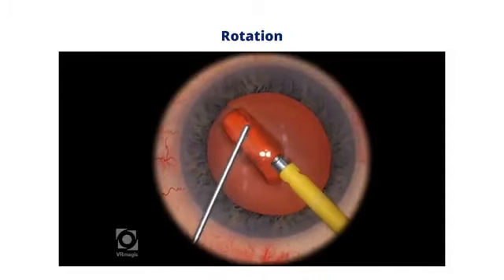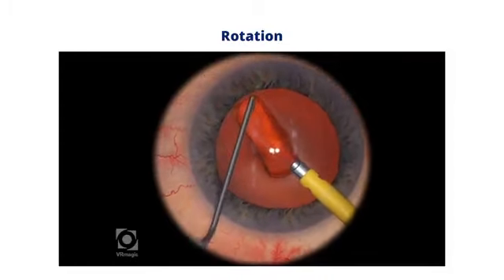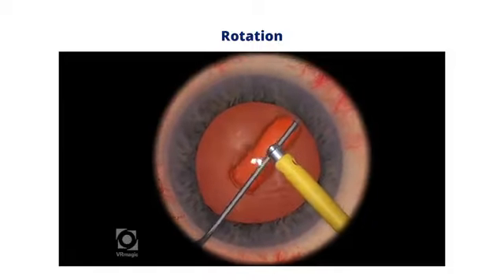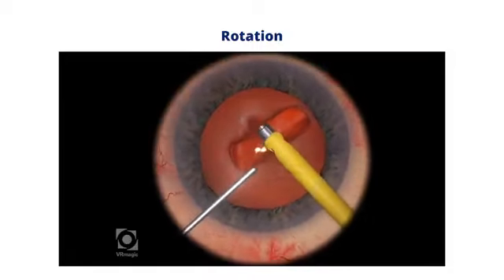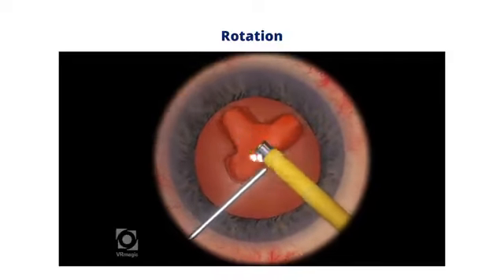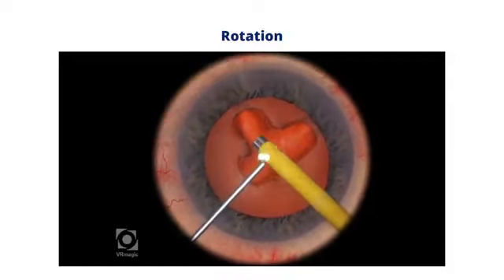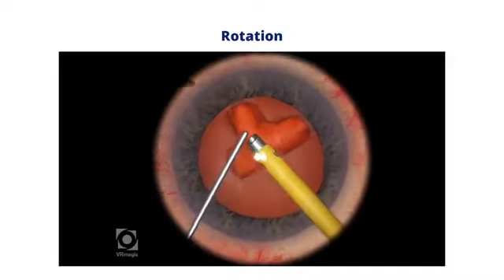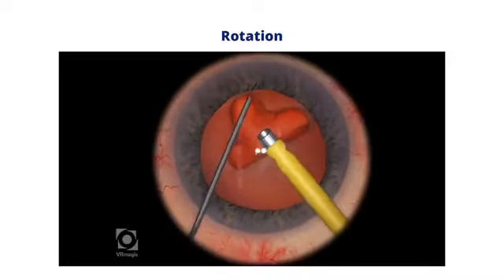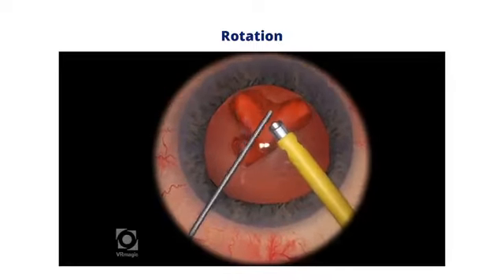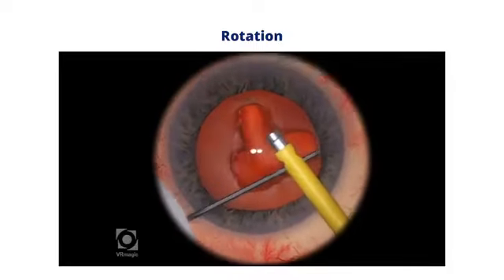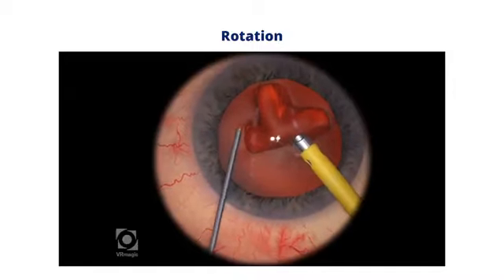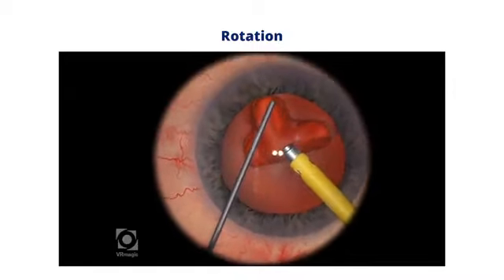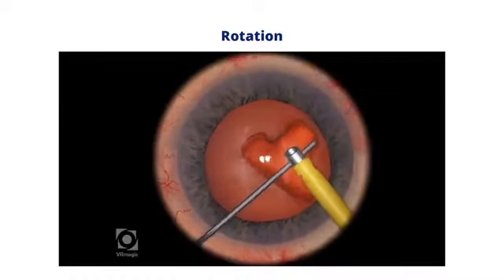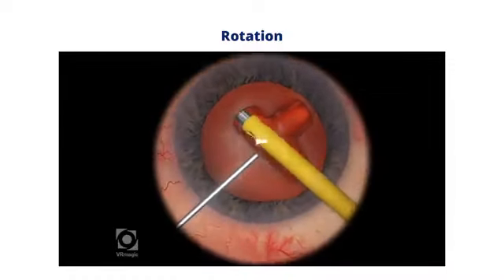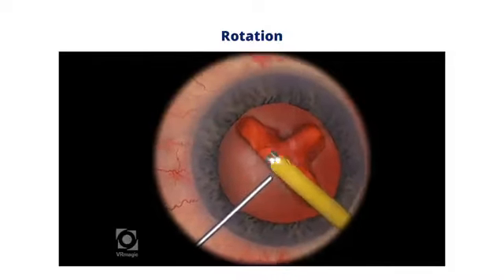When the first trench has been completed, the nucleus is rotated 90 degrees to make the second groove. The nucleus is rotated by placing a second instrument in the very bottom and the very end of the groove and applying a rotational force. The rotational force, or torque, is the product of the force applied and the distance of this force from the centre of the movement. The second instrument is therefore placed in the peripheral part of the groove. The phaco probe can be used to assist rotation at the other end of the groove when necessary. The second instrument is rotated between finger and thumb to produce the required angular rotation.